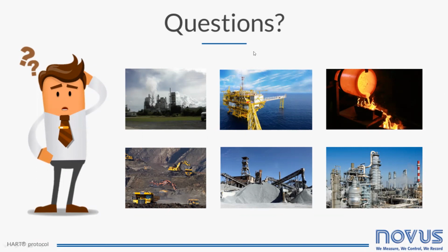Okay, now I would like to ask my colleagues the most common written questions. We have questions and answers here, guys. Yeah, we have one question right here about the HART. Does HART communicate using a 4 to 20 milliamp signal? The HART protocol uses two communication signals in the same current loop cable pair, the 4 to 20 milliamps analog signal and the superimposed digital signal. The 4 to 20 milliamps signal transmits the main measured value, while the digital signal contains information from the HART device, such as status, diagnosis, and configuration values.